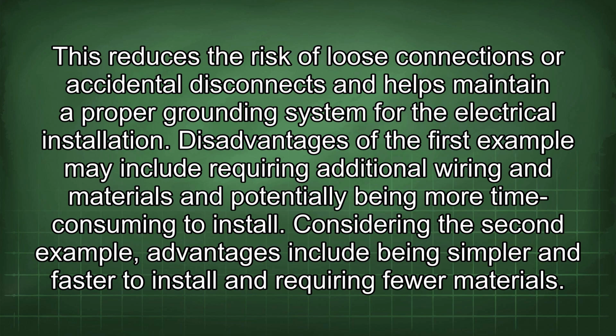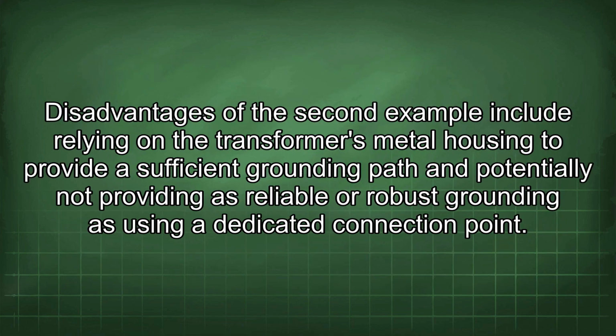Disadvantages of the first example may include requiring additional wiring and materials and potentially being more time-consuming to install. Considering the second example, advantages include being simpler and faster to install and requiring fewer materials. Disadvantages of the second example include relying on the transformer's metal housing to provide a sufficient grounding path and potentially not providing as reliable or robust grounding as using a dedicated connection point.